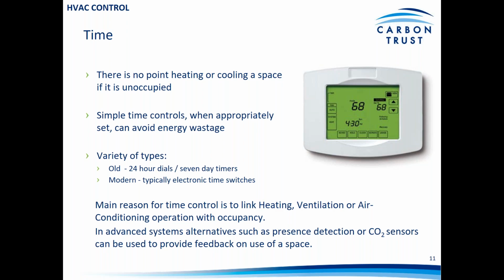So the main need for control is really to link your heating, your ventilation, or your air conditioning system with occupancy. And in advanced systems, you may use the likes of presence detection or indeed CO2 sensing, which we'll come on to, to provide feedback on the occupancy of the space, and that'll allow you to adjust the ventilation or the heating and cooling requirements.